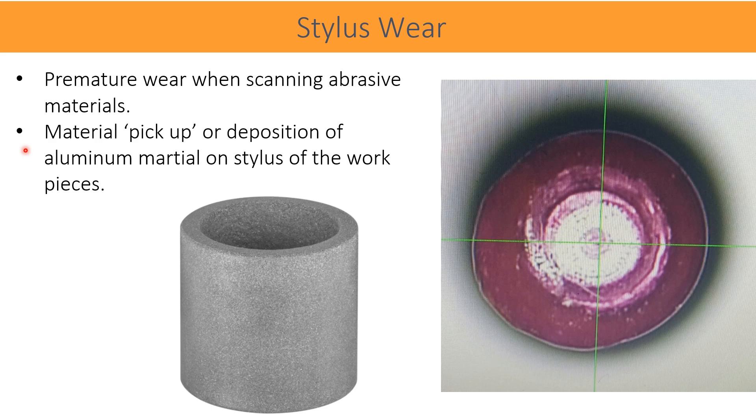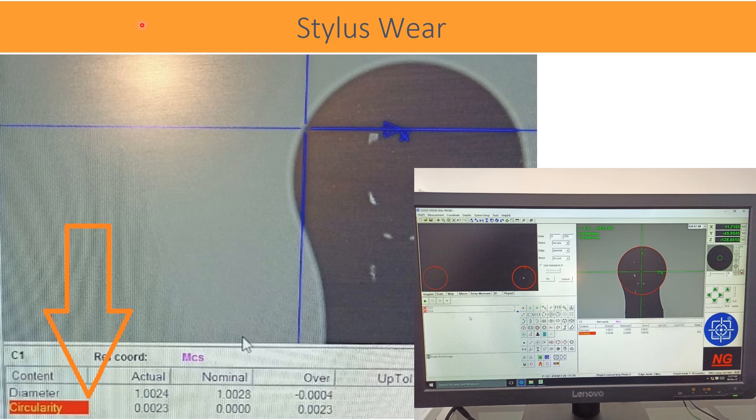The image we see here is after enlarging many times on a video measuring machine, sometimes called a VMM machine. Mostly to the naked eye, it is very difficult to find wear on the stylus. In larger zoomed images, the real shape change is easily seen.